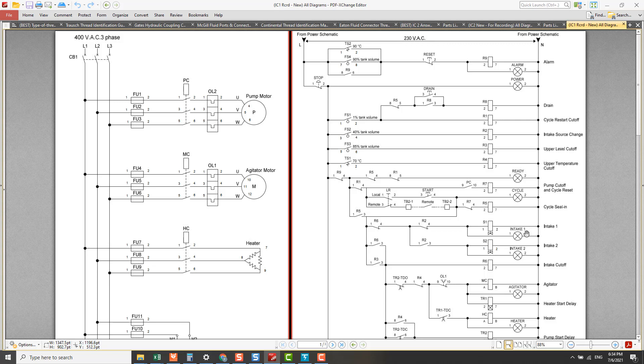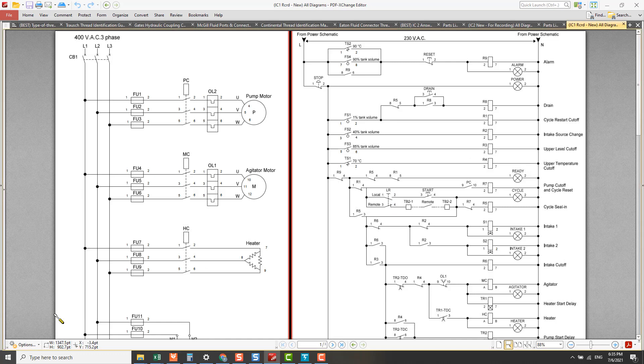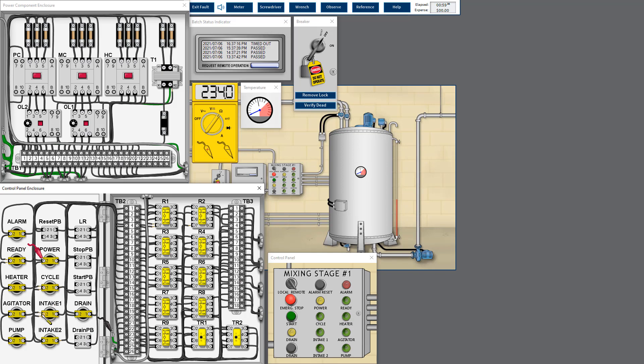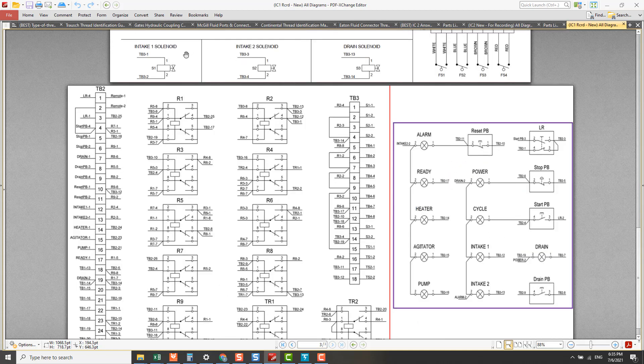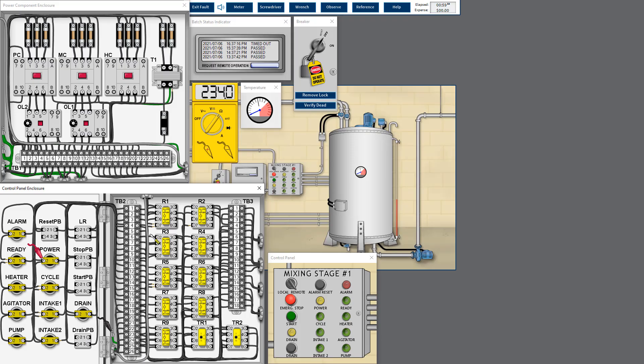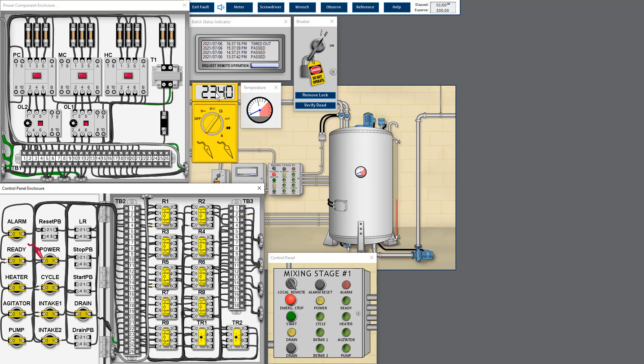Opening cycle 2, Intake 1-2, R5-7, and S1-2. S1-2 connects to TB3-2, so I open TB3-2 here. Then R5-7. The resistance remains the same, meaning no earth fault before the load in this section.